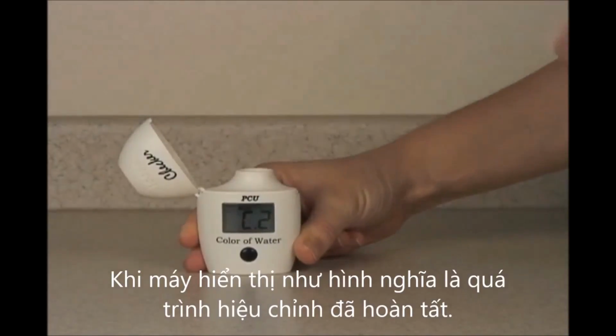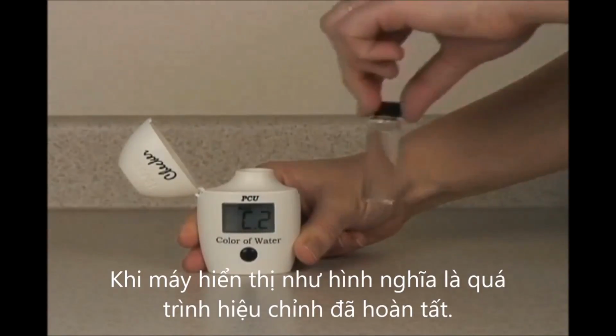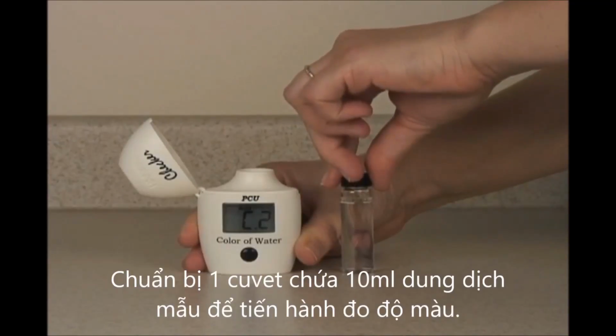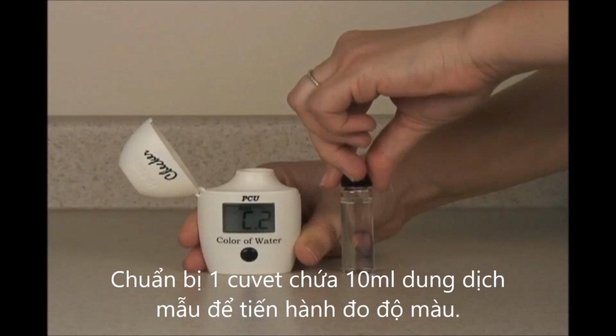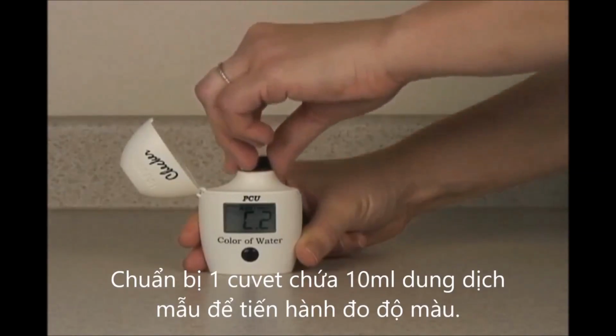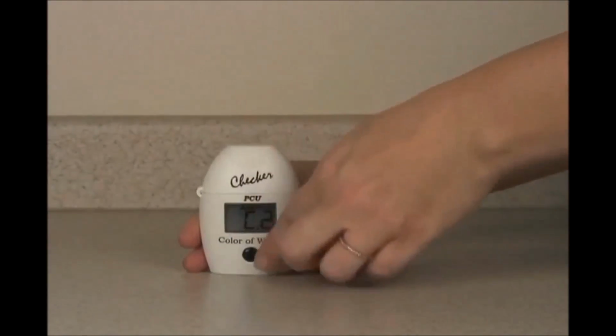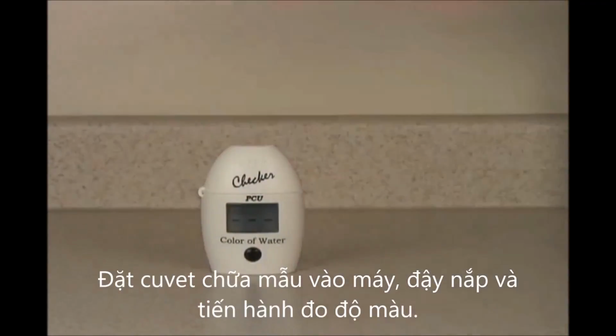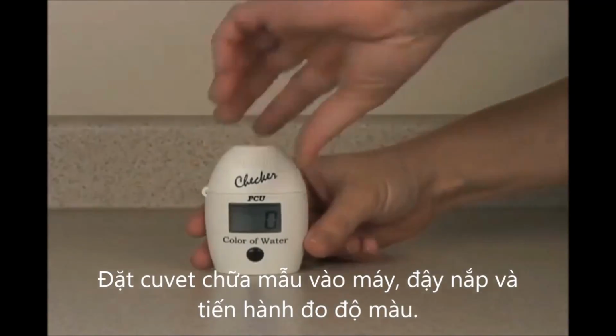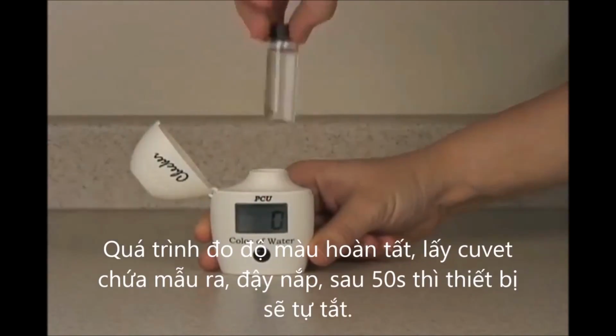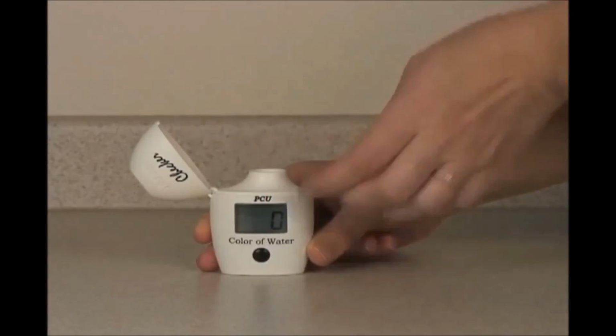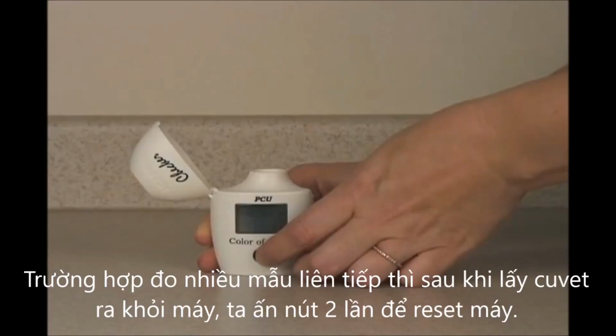Remove your blank, and you fill the next cuvette with 10 milliliters of your sample water. Put your sample in the checker and press the button again to take the measurement. Record this value. Remove your apparent color sample and press the button twice to restart the meter.